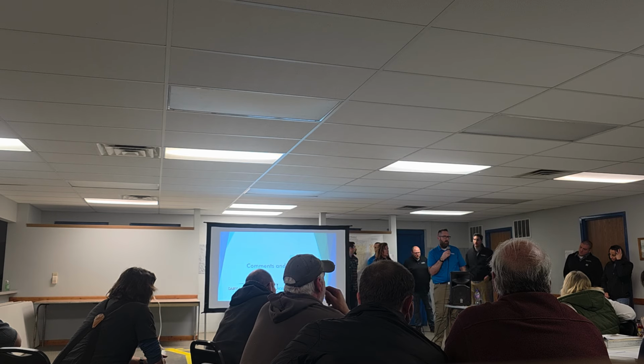Yeah. So it's more of a question of efficiency on how to transmit that power, and then also a question of what's the usable voltage by the end consumer. So, into your house, you're running 240, and so that all has to get stepped down. And it's a question of cost of the transformations from 765 down to a lower distribution line. And so it's easier to do a transformation from like 161 further down to distribution and then ultimately into the home. So having both facilitates both the larger power transfers and then easier efficiency to transmit into the homes.